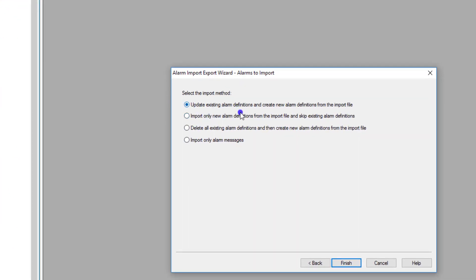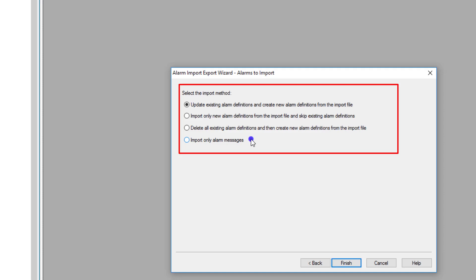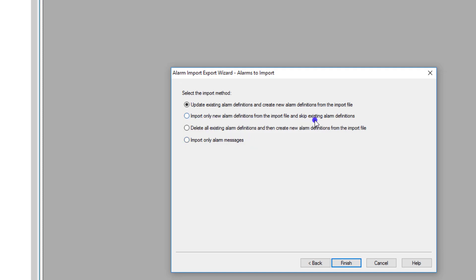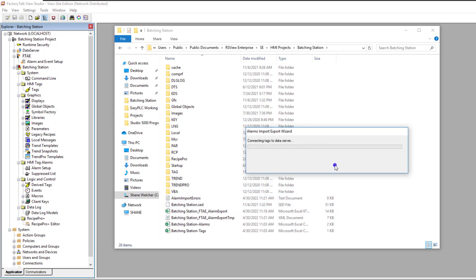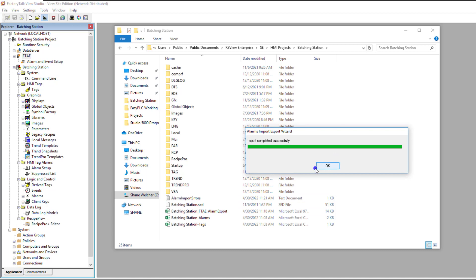Click Next. At this point you have options: update existing and create new ones, import only new ones and skip existing ones, delete, or import only alarms. I personally like to use 'update and create new ones' as the default. However, if you already have some alarms in there, it may be safer to import only new tag alarm definitions and skip the rest. I'll use the first option. It's converting — and it successfully added that into the system.